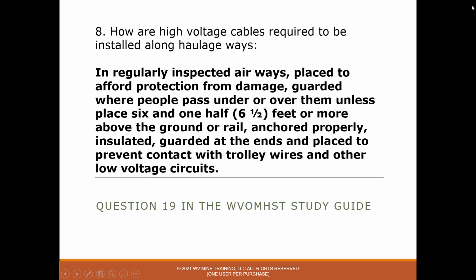Number 8, how are high voltage cables required to be installed along haulage ways? And the answer is in regularly inspected airways, placed to afford protection from damage, guarded where people pass under or over them unless placed 6 1/2 feet or more above the ground or rail, anchored properly, insulated, guarded at the ends, and placed to prevent contact with trolley wires and other low voltage circuits.